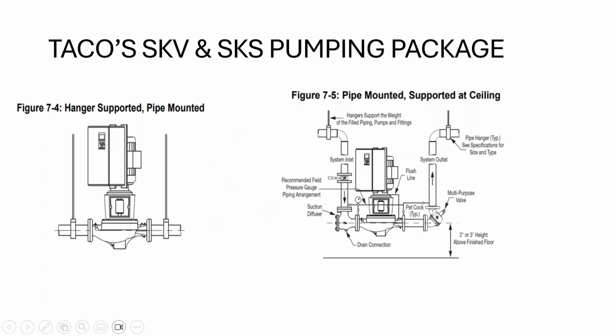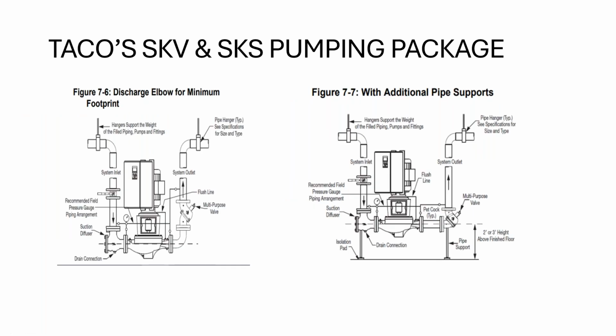Did I do that right? There we go. And there's a discharge elbow for minimum footprint. So these pumps should take up less room in a mechanical room. There's that suction diffuser on the suction side, with the straightening vanes in it. And if you get that, you've got a discharge elbow on it, and you can go straight up and hang it like that. That's a pretty neat package as far as I'm concerned. So something to consider in that regard.